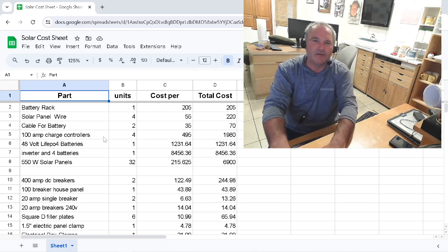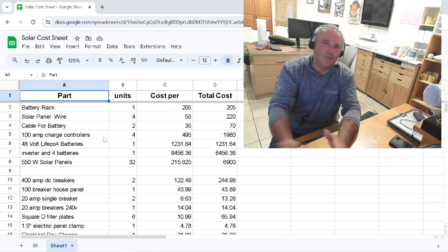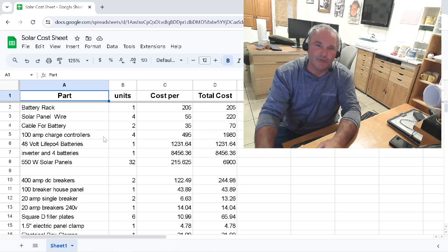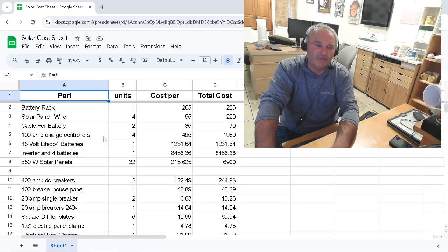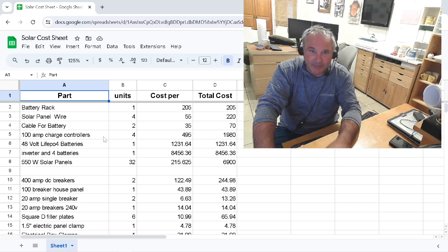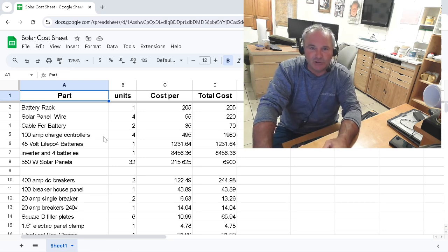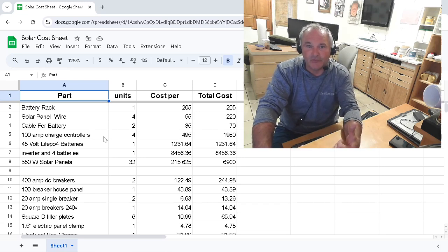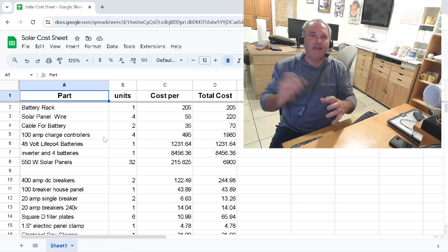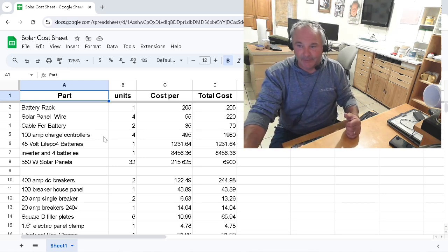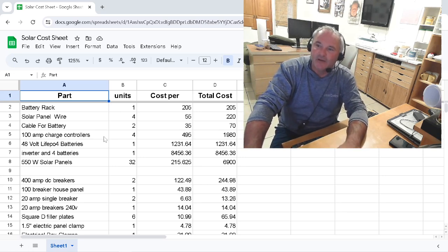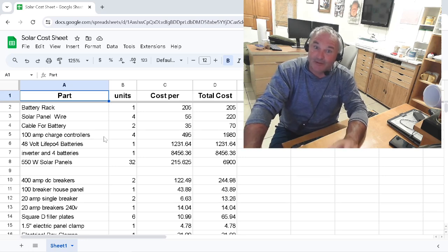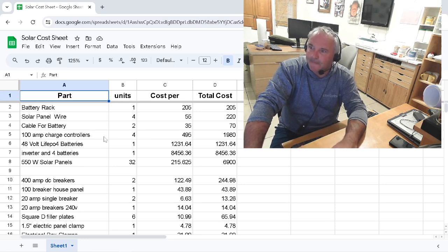The 100-amp charge controllers. Now, they have a 60-amp and a 100-amp charge controller. Let me just say, I bought the hundreds because we have so much power up on the roof. Those solar panels will produce 17,400 watts of power per hour on the peak heat, peak time of day. The 100-amp charge controller can handle 5,200 watts input from those solar panels. The 60-amp will not do as much. So for me to break it down, I had to buy the better charge controllers so I wouldn't have to buy so many of them and so many of the combiner boxes up on the roof and all that kind of stuff. So it was just cheaper to go this route. So there's four of those. Those are $500 a piece, but they work great.